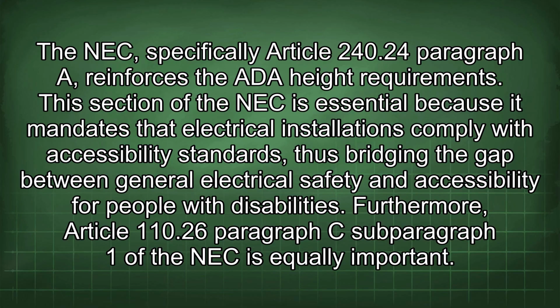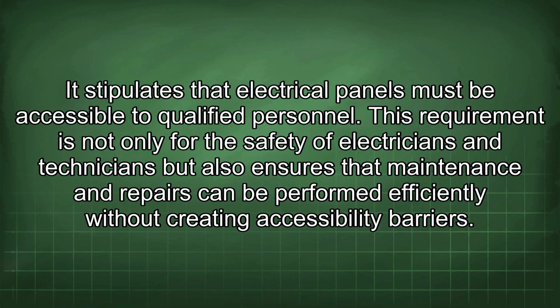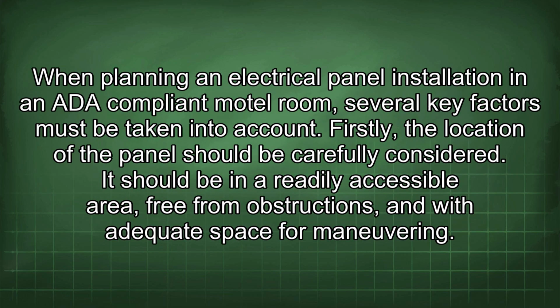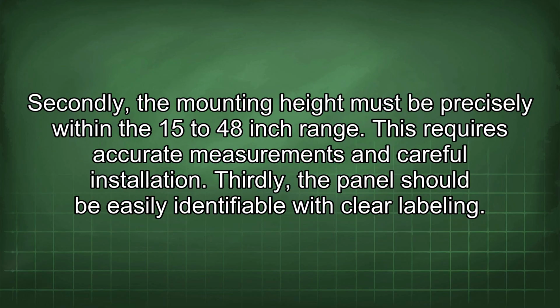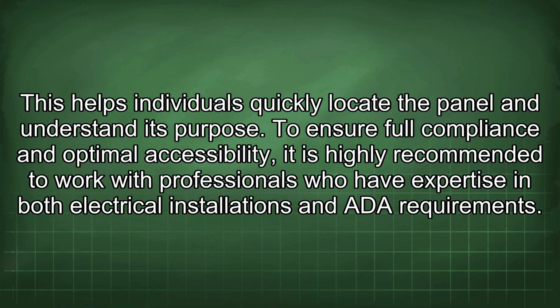Furthermore, Article 110.26 paragraph C subparagraph 1 of the NEC is equally important. It stipulates that electrical panels must be accessible to qualified personnel. This requirement is not only for the safety of electricians and technicians, but also ensures that maintenance and repairs can be performed efficiently without creating accessibility barriers. When planning an electrical panel installation in an ADA-compliant motel room, several key factors must be taken into account. Firstly, the location of the panel should be carefully considered. It should be in a readily accessible area, free from obstructions, and with adequate space for maneuvering. Secondly, the mounting height must be precisely within the 15 to 48 inch range. This requires accurate measurements and careful installation. Thirdly, the panel should be easily identifiable with clear labeling. This helps individuals quickly locate the panel and understand its purpose.